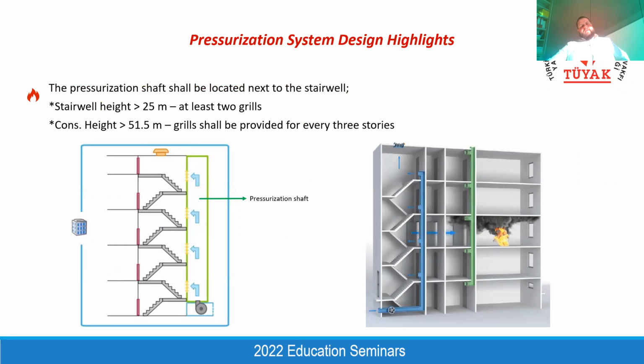staircase exceeds 51.5 meters. If the staircase exceeds 51.5 meters, at least we have to provide pressurization air for every 3 floors at maximum. It means in every 3 floors, we have to have a grill that gives us fresh air from the pressurization shafts. But for high-rise buildings, we always prefer to have a grill on every floor, because it becomes easier: if you put grills on every floor, the grill sectional area will become much smaller than having pressurization grills for every 3 stories.